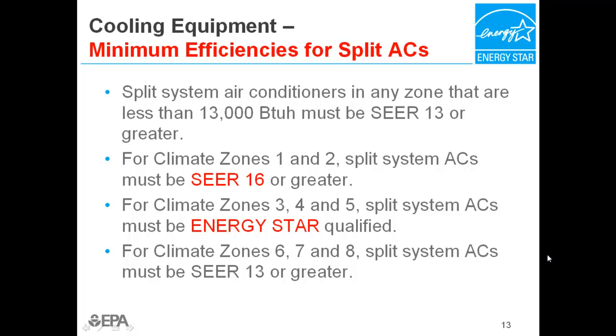Due to availability, split system air conditioners smaller than 13,000 BTUs per hour do not need to be Energy Star qualified, but must meet the federal standard of SEER 13. In the prescriptive path, due to their larger cooling loads, split system air conditioners for climate zones 1 and 2 have to exceed Energy Star criteria with a SEER 16 or better. Split system air conditioners in climate zones 3, 4, and 5 have to be Energy Star qualified. Due to the smaller cooling load, split system air conditioners in climate zones 6, 7, and 8 only need to meet the federal standard of SEER 13.